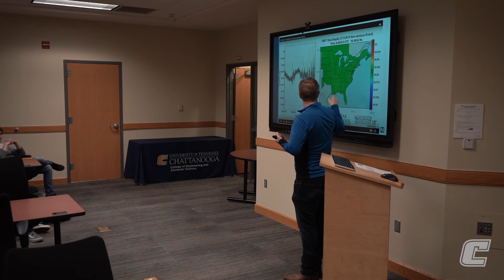Actually, this was 0.25. The natural frequency is around 0.24. So it was really close. So this unit's oscillating at 0.25 hertz, and it starts exciting this natural mode that's just made up of, you know, the transmission grid, and it gets amplified because of this resonance effect. So that's why this little 200 megawatt unit in Florida was moving the whole grid. What was interesting is we went back and listened to some of the calls, and of course the operators in Tampa are like, yeah, we're having problems, but this is a little unit, you know, we're not causing this up in Wisconsin, we're in Florida, you know, don't you know that?